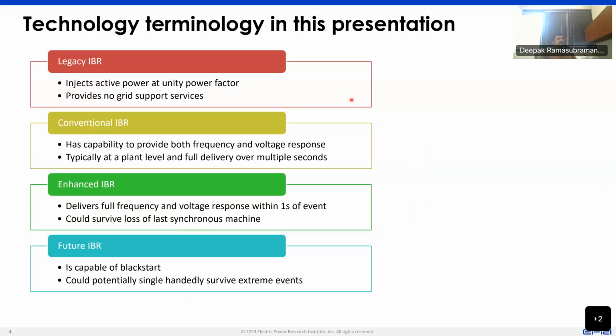So the way these categories are, I might speak quite a bit about legacy IBR. What is legacy IBR is essentially the past system, wherein we have the inverter-based resource injecting active power at unity power factor and not really providing any grid support service. So it's just injecting active power, and those kinds of devices would be classified as legacy inverter-based resources. We move on, we have what can be called a conventional inverter-based resource, which would constitute the majority of inverter-based resources that have probably been connected in the past decade or so. These have the capability to provide voltage and frequency response, but this capability is typically at the plant level, and full delivery of this service may be over a period of multiple seconds. So it's not that the inverter-based resource in our system cannot do frequency response or voltage response. It's just on a much slower time scale, and it's usually at the plant level.